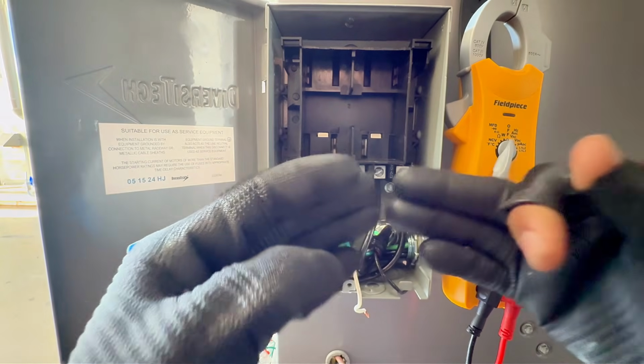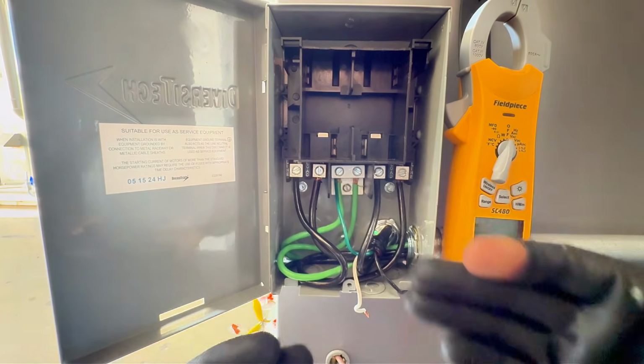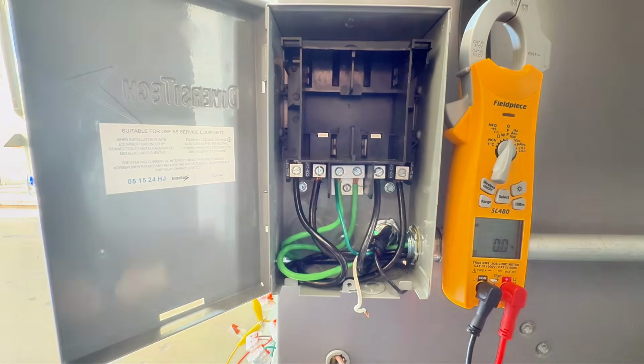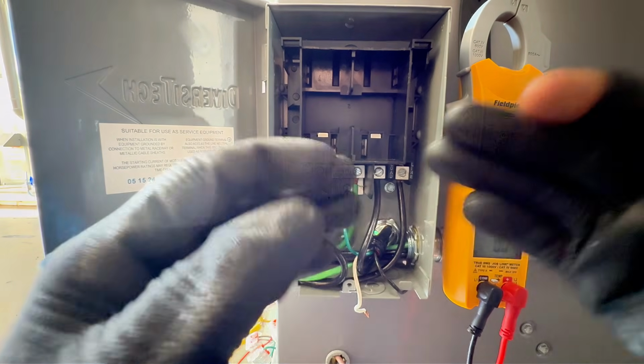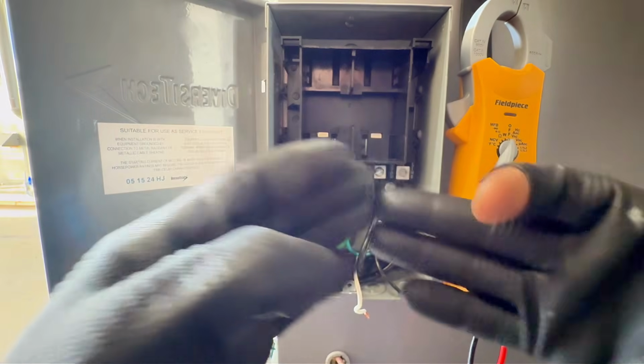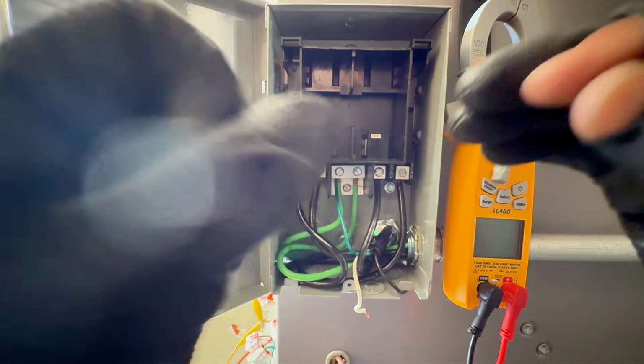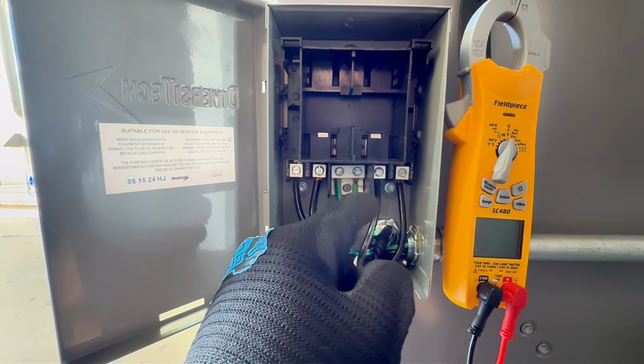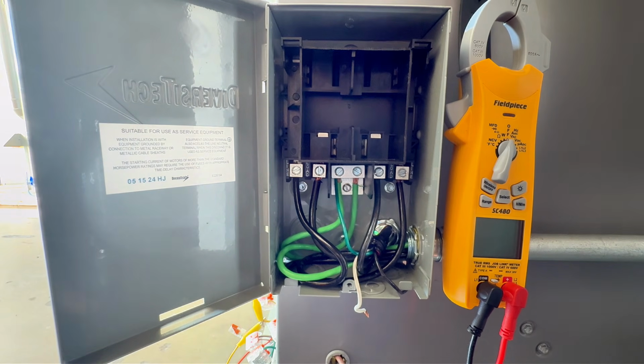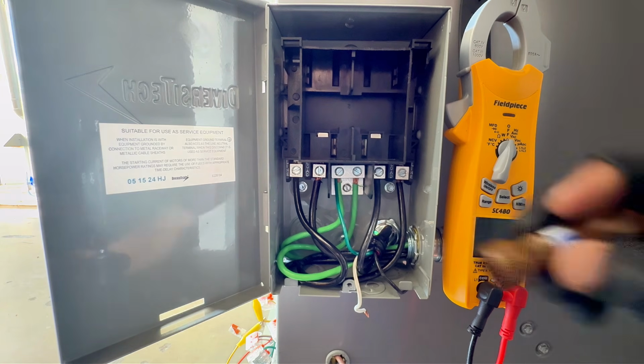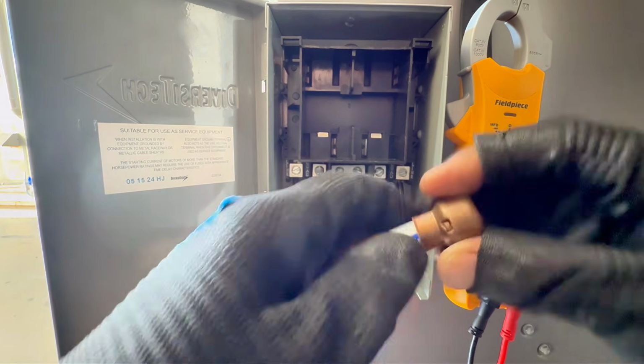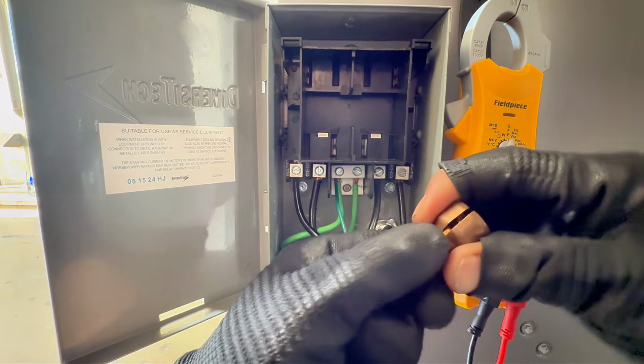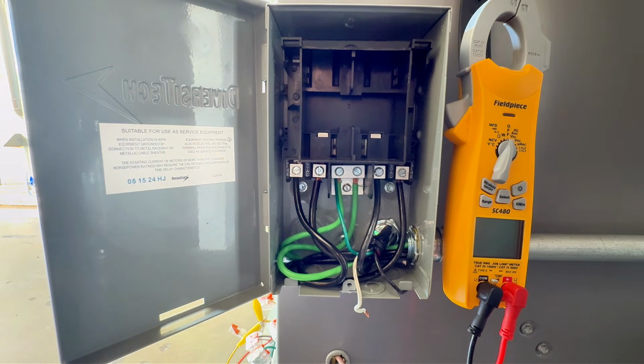So when those wires are not tied, it ends up becoming a resistor instead of a conductor. So they have to be tied. Everything where you're going to have a lot of current going through, there's going to be a lot of heat. It has to be tight. And in this case, this is a bad example on this one. On this one here too, what I did over here, the fuse is loose as well. You see, this is loose on this side. So I intentionally created these issues.